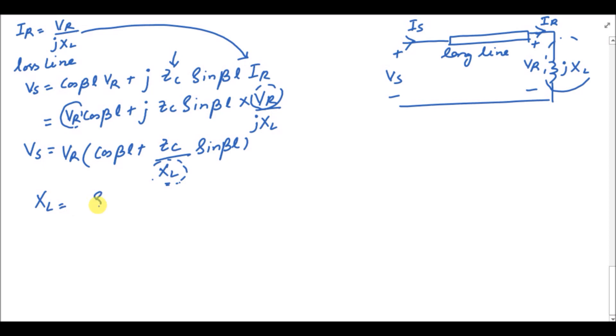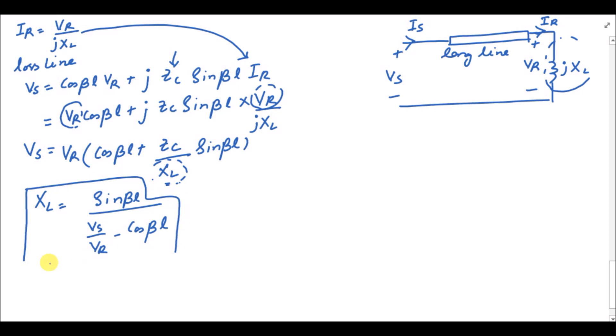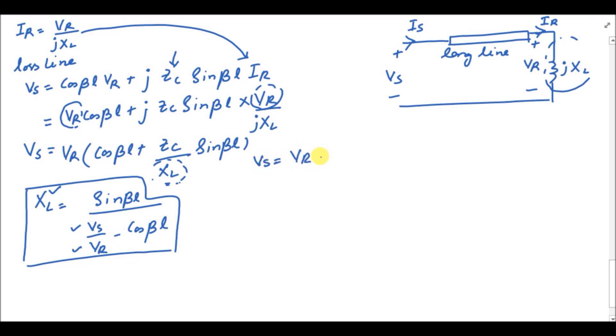Taking XL to the other side of the equality and solving, we get: XL = Zc·sin(βl) / (Vs/Vr − cos(βl)). This is the formula for calculating the reactance value when you have an overvoltage problem at the end of the transmission line. You put the sending-end voltage for Vs and the receiving-end voltage value you want to maintain for Vr.